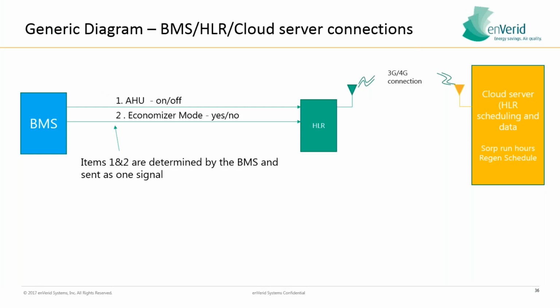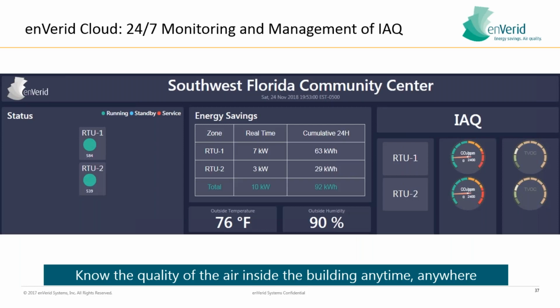I mentioned cloud integration here, so we do have the 3G, 4G connection showing unit status and whatnot. We also integrate with the BMS system. If economizer mode is on, we go into standby, and we're typically running during the traditional run hours of a building. So all those set points are available from our support tools as well. And this is a snapshot of the SCADA, of the actual reporting that we have, so you can see whether or not units are running, energy savings, modeled energy savings, as well as CO2 and total VOC outputs as well.